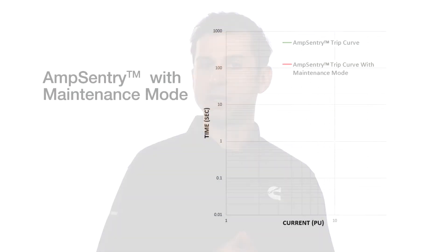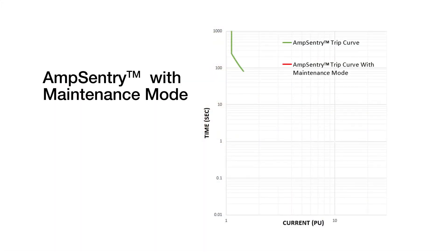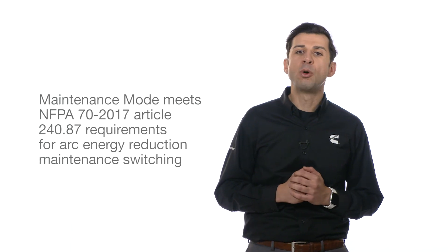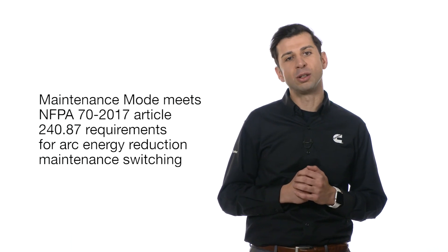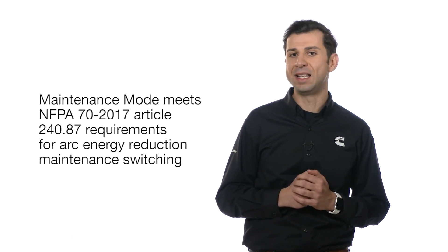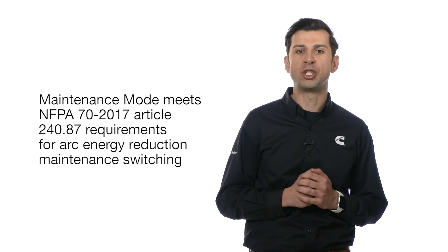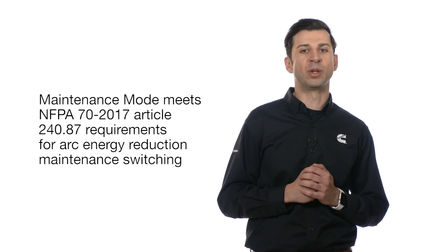Maintenance mode is similar to a circuit breaker arc energy reduction function. When maintenance mode is enabled, the generator set shuts down instantaneously in the event of a short circuit, bypassing all time delays. Maintenance mode meets NFPA 70 Article 240.87 requirements for arc energy reduction maintenance switching.